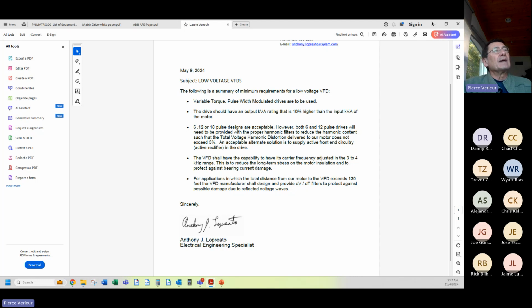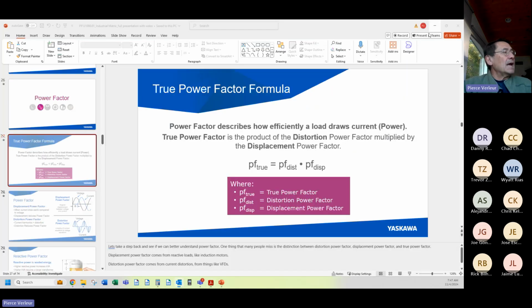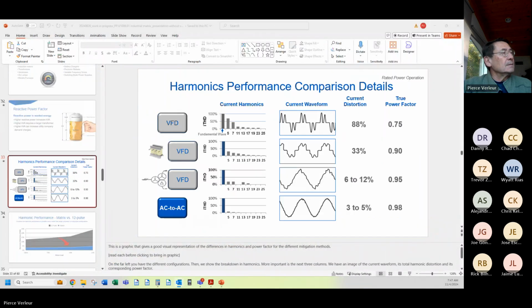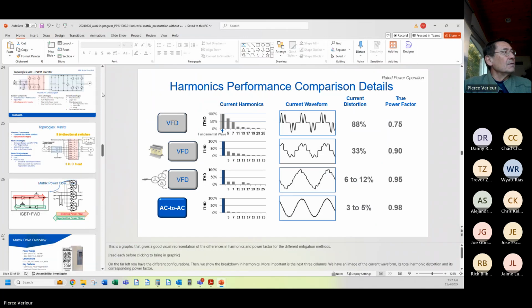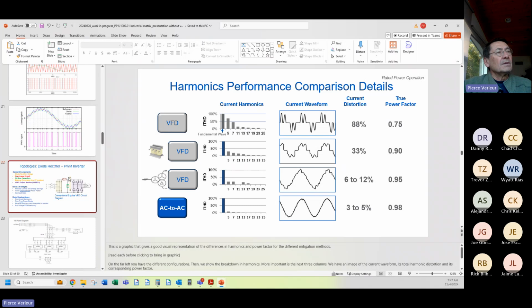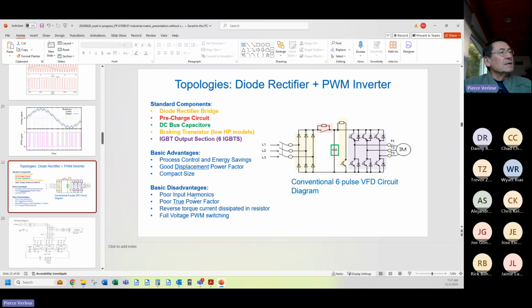So with that in mind, let's go back to this. How can that be when, in comparing the topologies of the drive, there's your variable frequency drive. Remember, this variable frequency drive with all the filters up front here, 6, 12, 18 pulse, is the same output to the motor. The filters go here, right?